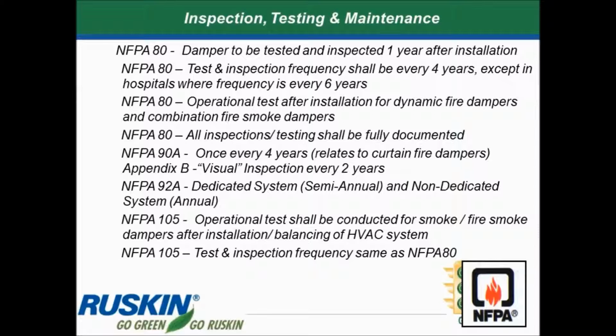Life safety dampers ought to be tested and inspected on a regular basis. There are a lot of guidelines. NFPA 80 talks about it, testing the damper 1 year after installation, and then it should be tested every 4 years after that. There are various other codes and recommendations for testing at different intervals, but the problem is that it's not really enforced and very few people do it faithfully on a regular basis. And so quite often a damper will go 2, 4, 8, 10, 15 years without anyone ever looking at it. And then if it ever needs to actually work in the event of a fire, all bets are off on whether it will work.